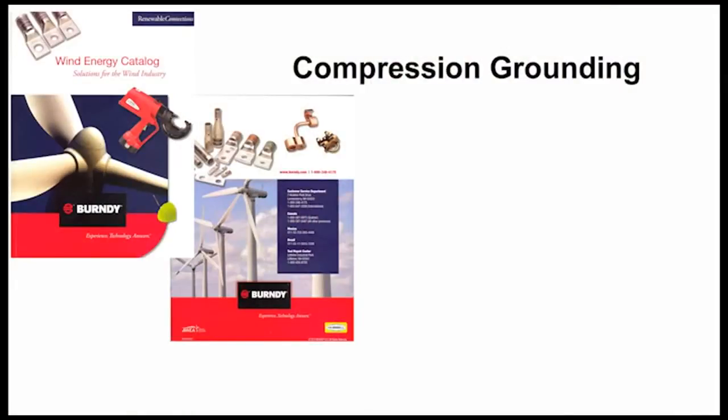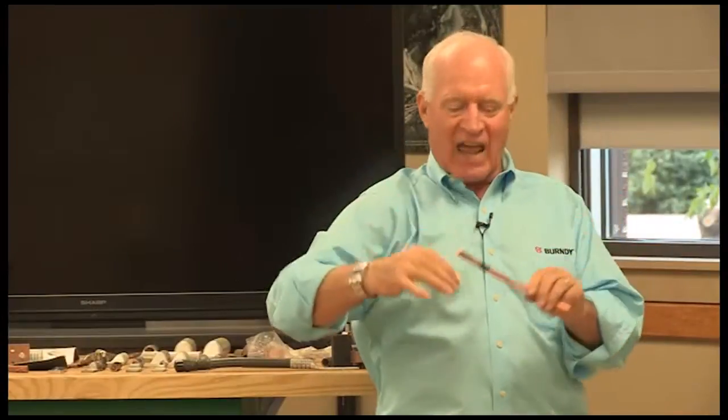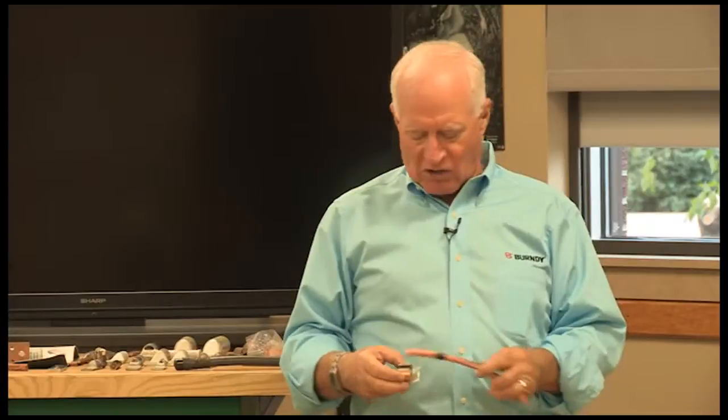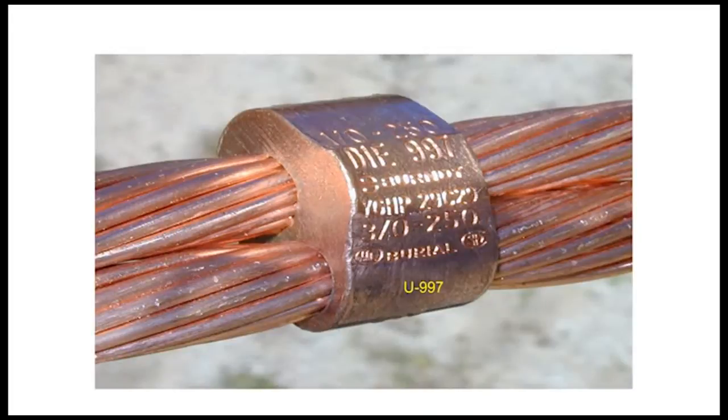Compression grounding. We're taking the copper cable and a copper connector. This copper and this connector the exact same materials. Under a certain amount of force when I put it into the crimping tool and I apply the 12 tons of force to encircle this connector onto this cable. Two like properties under a certain amount of force blend together to become one.